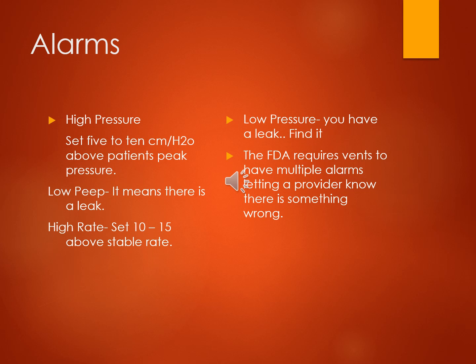High respiratory rate, we're going to set it 10 to 15 breaths above a stable rate. That gives us an idea if the patient is a little anxious, if they're uncomfortable, or if things are changing in their airway. Low pressure, again, is telling us that you probably have a leak somewhere, so you want to make sure you're looking up and down for it. We always tell people you can either go from the ET tube to the circuit, or the circuit to the ET tube, and figure out where it's at.